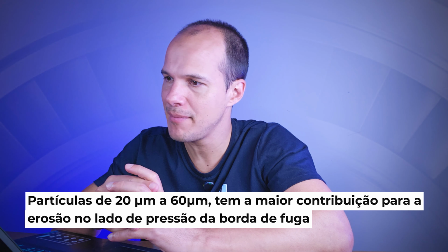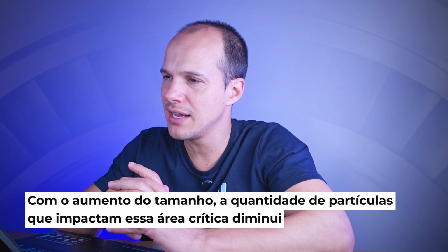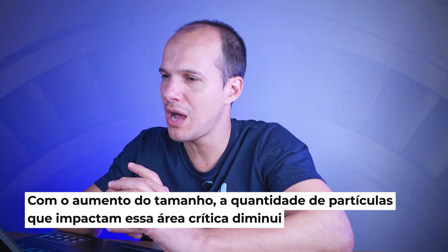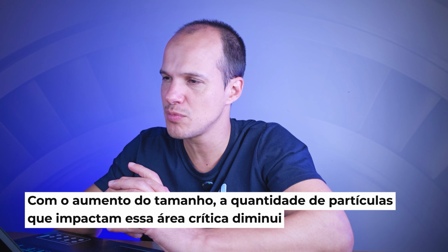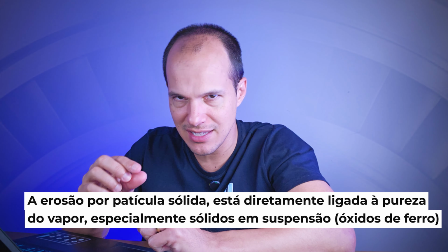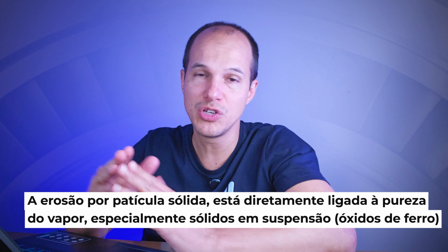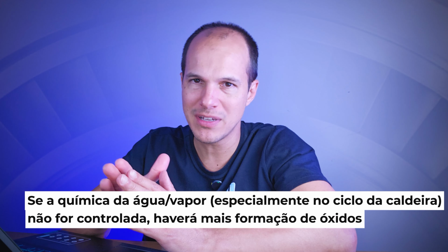And the ideal range of this distribution combines a very high impact speed, from 250 to 300 meters per second, with a specific angle of incidence, which tends to be flowing exactly along with the steam. And it will catch there on the edge of the diaphragm block outlet, and it will end up damaging the output. And with that, the process of loss of efficiency is progressive. And the steam begins to be directed towards a suboptimal point, which won't match the designed profile.